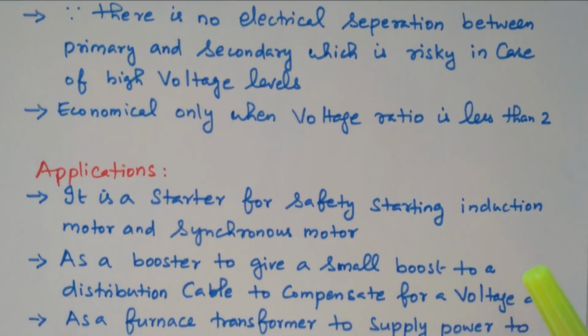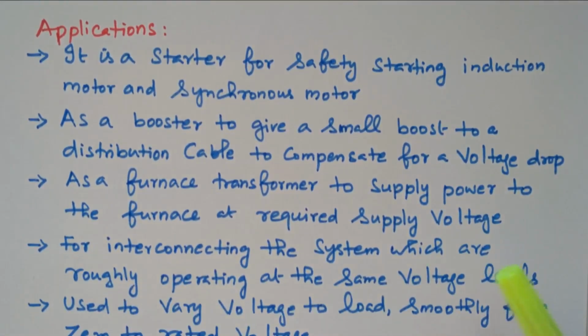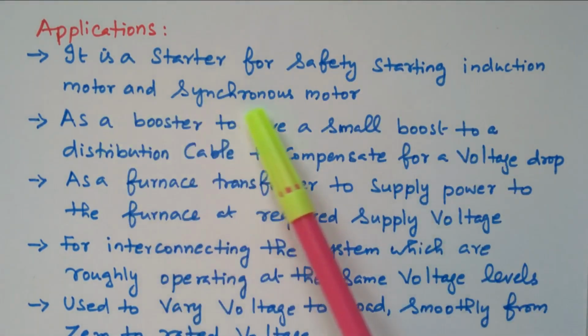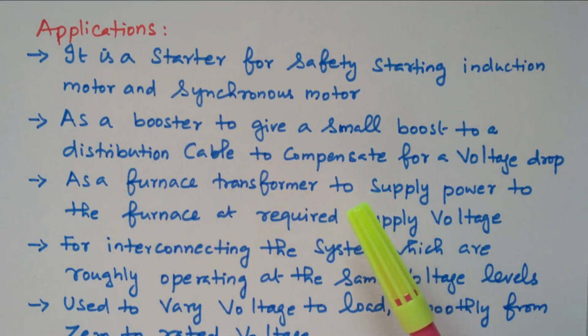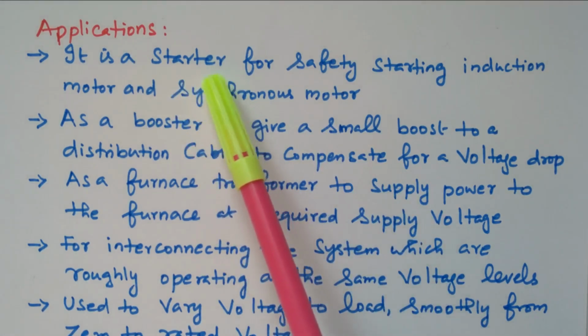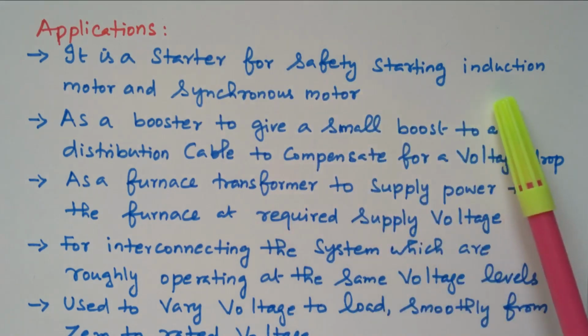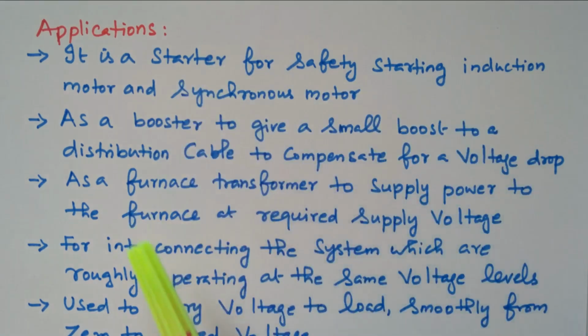We will see the applications of this auto transformer. It is used as a starter for safe starting of induction motors and synchronous motors. With the auto transformer, by adjusting the voltage, it is slowly applied to the motor. So it acts as a starter, right? The voltage given to the motor is slowly increased, so that the speed of the motor also slowly increases.